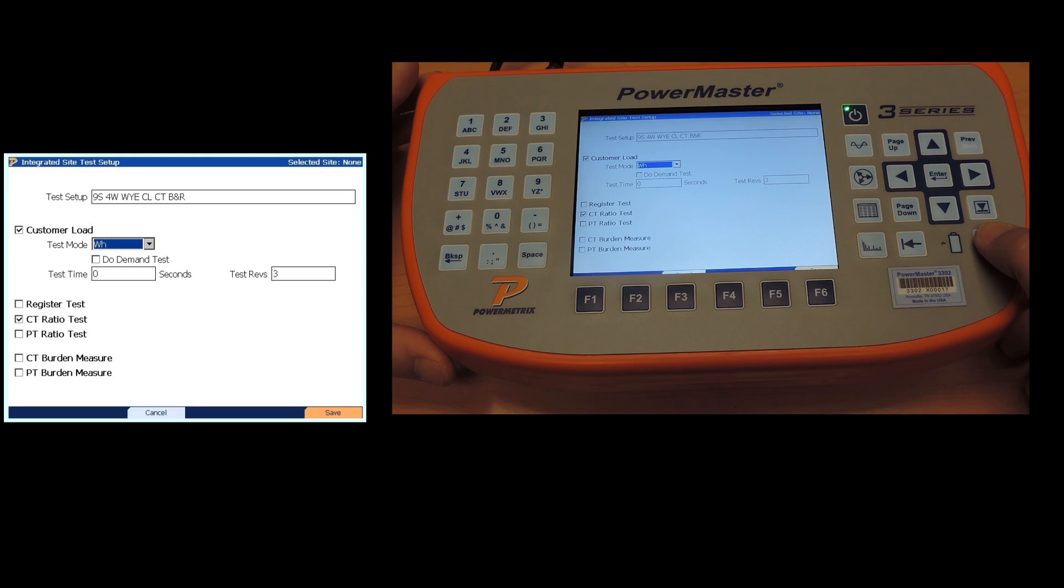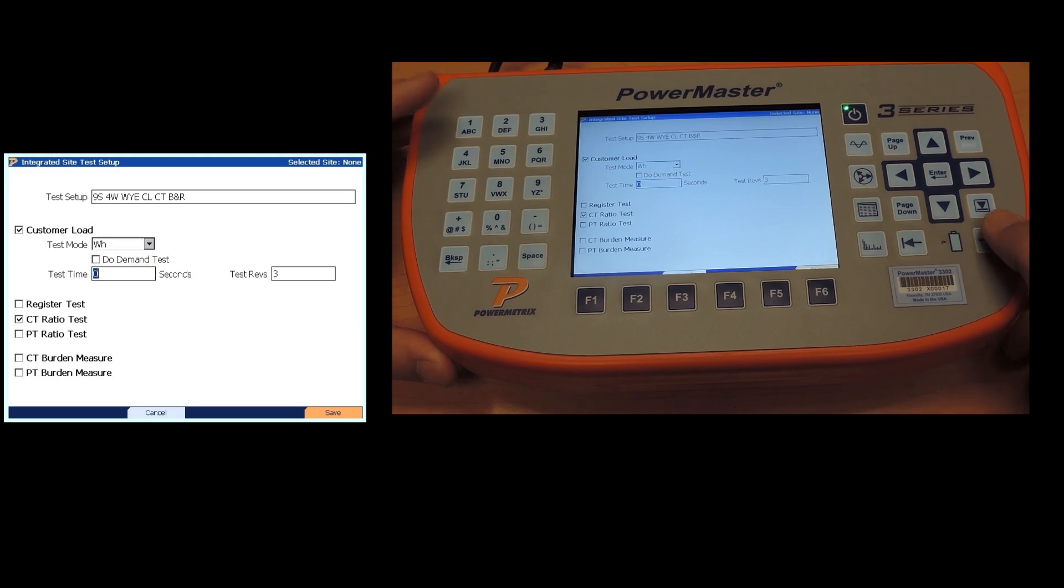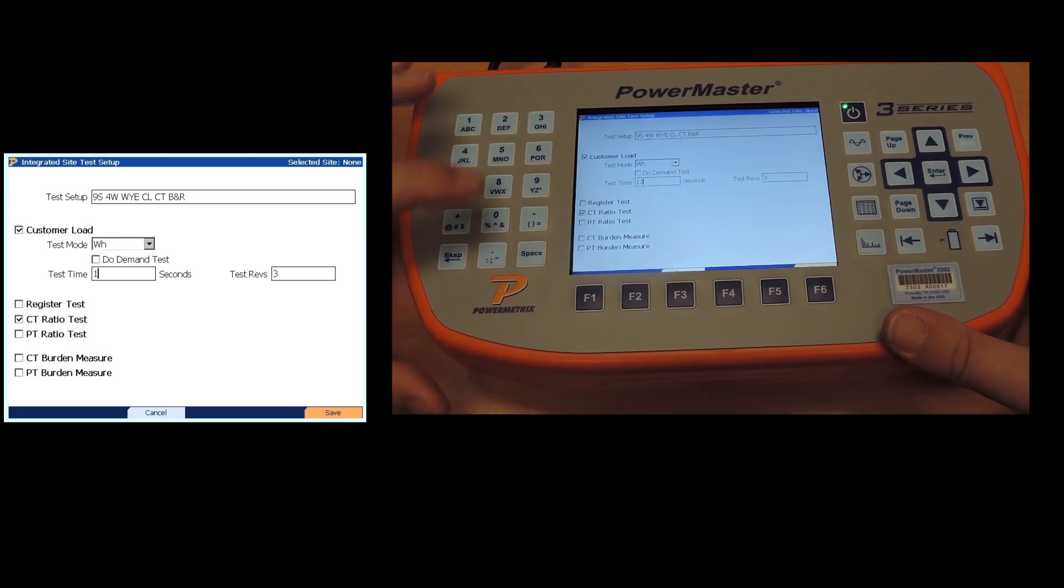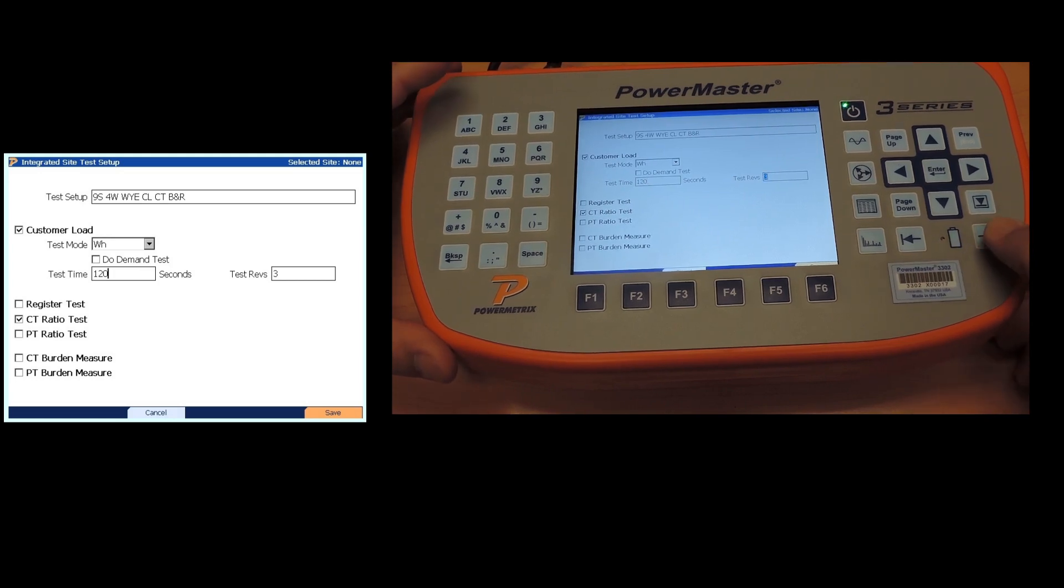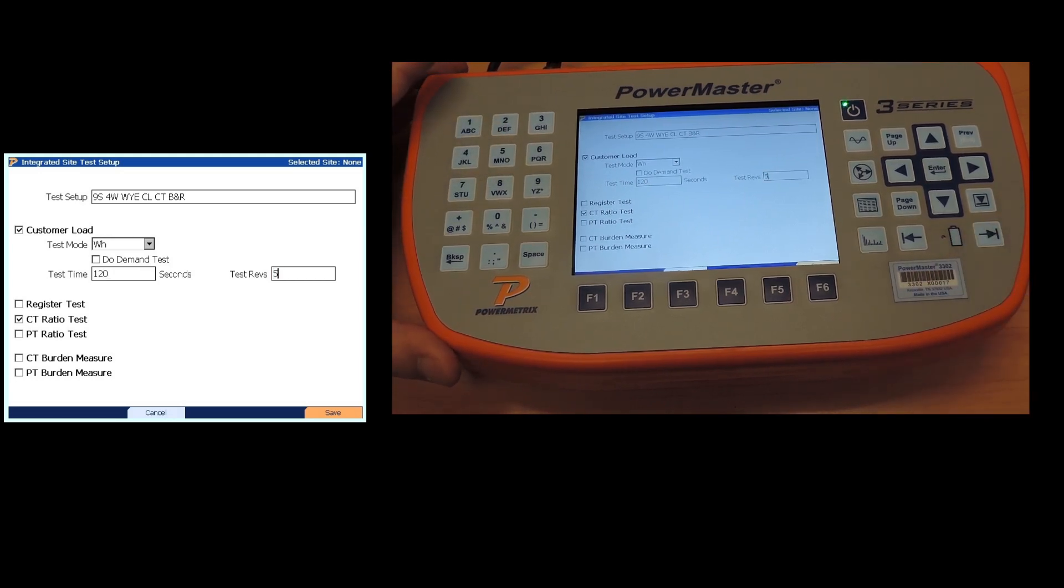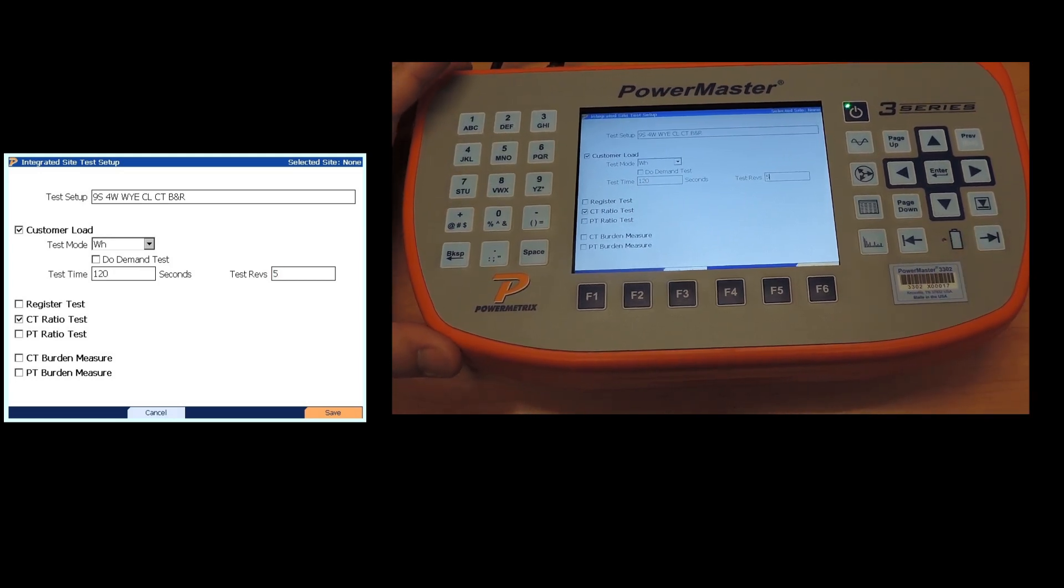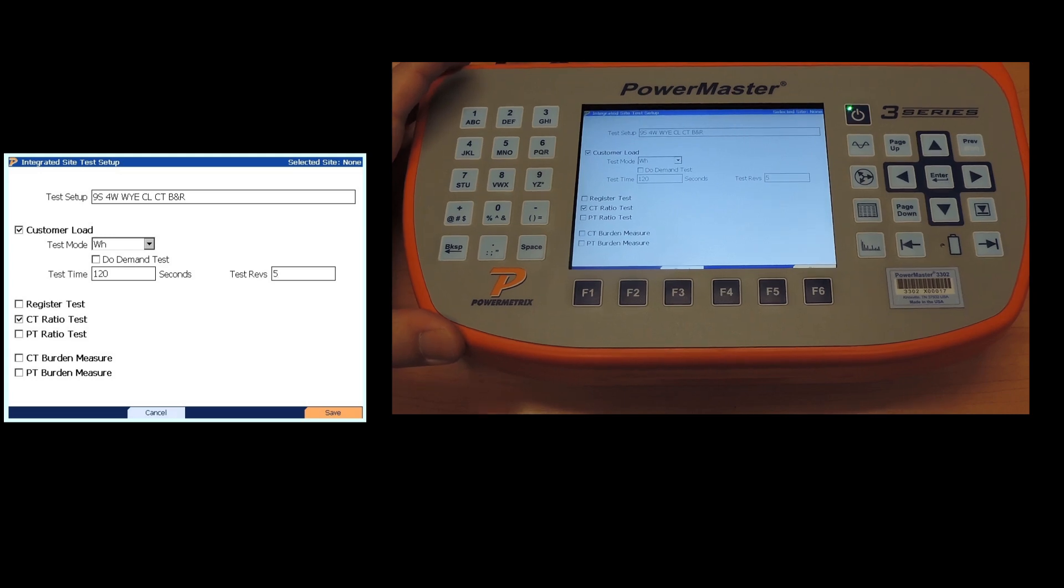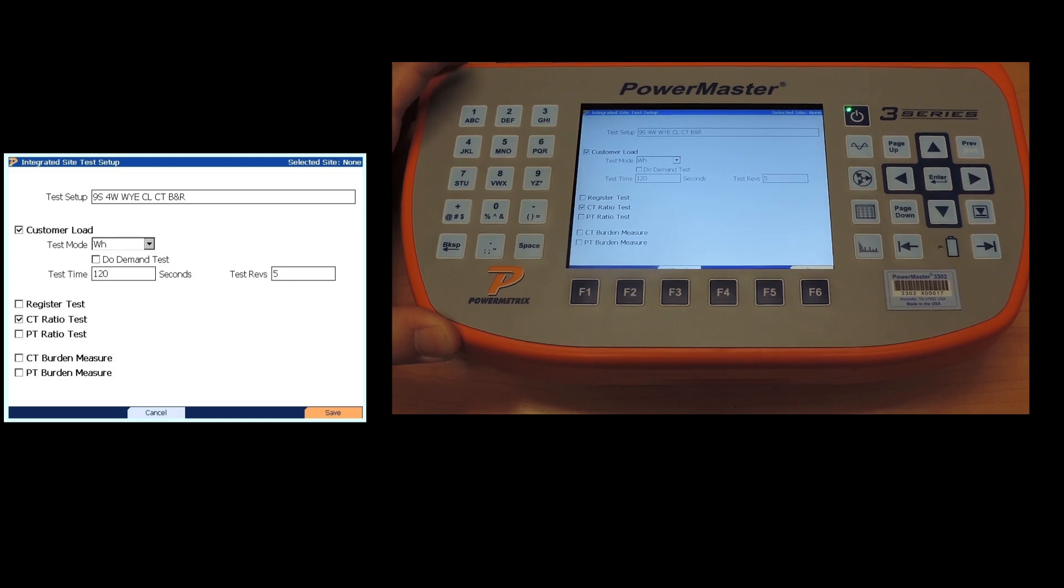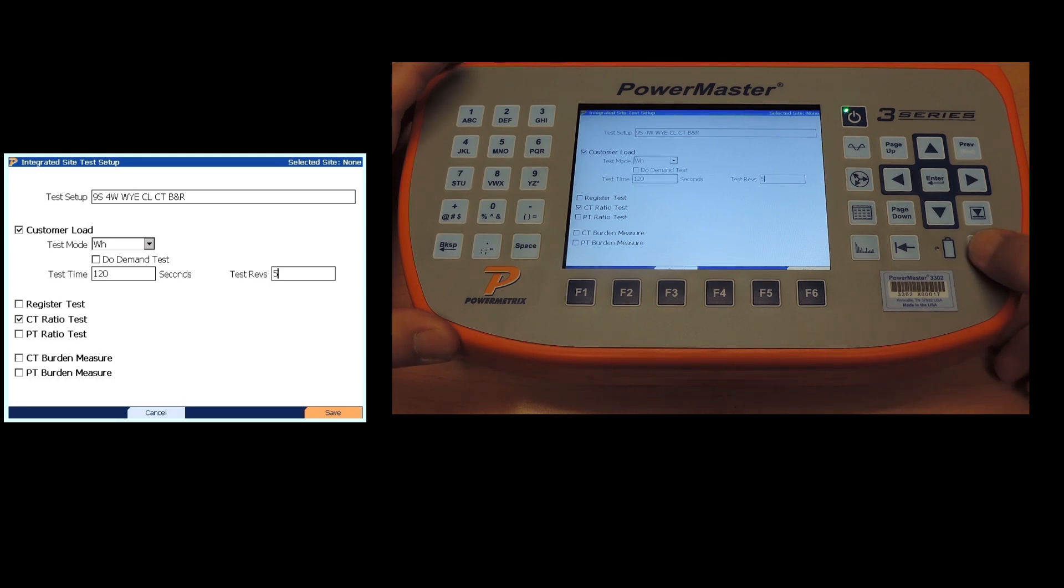If not, we'll be doing a test time and I'll do 120 seconds and five revolutions. If it is a lightly loaded system, the longest you stand there will be two minutes. If not, five pulses will be pretty quick. The two fields are mutually exclusive. Whichever it reaches first is the one it closes on.